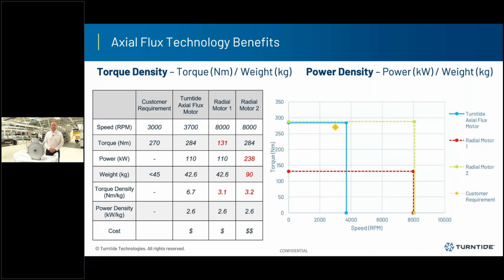So at the top, I've given a brief definition of these concepts. Torque density is the amount of torque that can be delivered divided by the weight. Power density is power delivered by the weight. And this is often used as a benchmark between different motor technologies. What I wanted to speak to you today about is the benefits that Axial Flux technology gives over radial flux technology. So in the table on the left-hand side, I've detailed out an example Turntide motor against some equivalent radial machines. In radial motor 1, we're comparing to an equivalent machine with the same power level, so an equivalent 110 kilowatts, with a higher speed, which is typical of radial machines.